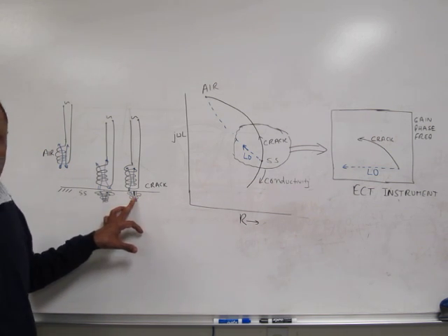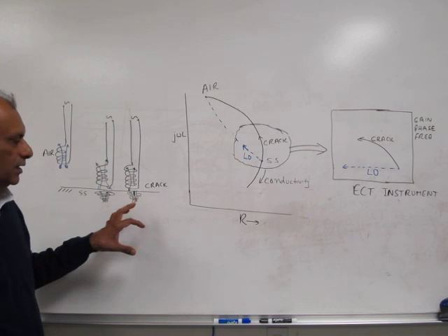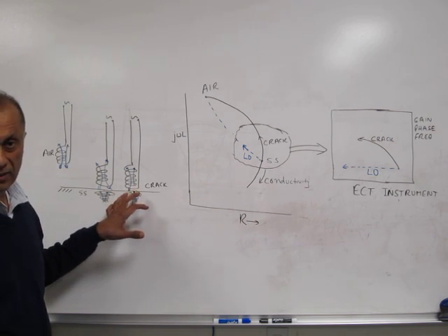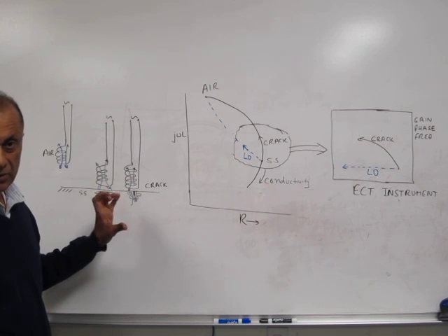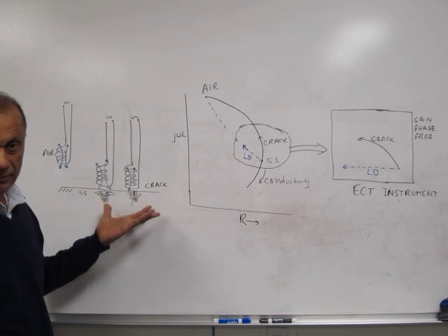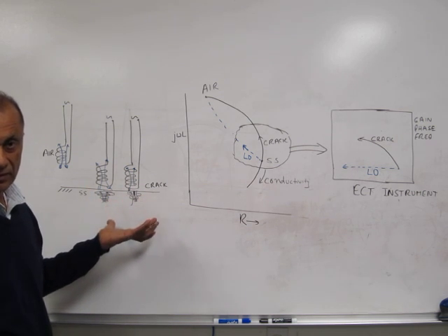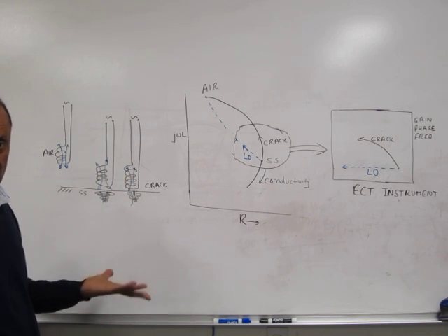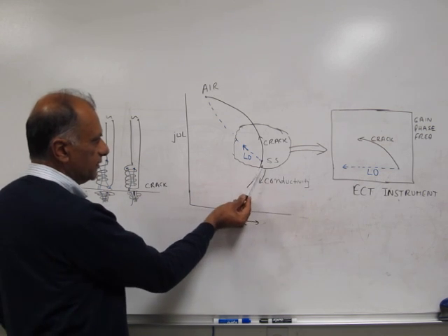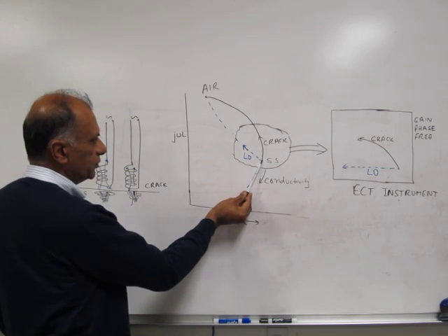As we scan the surface of the stainless steel and encounter a crack, the crack distorts the eddy currents in the material, thereby distorting the magnetic field. This change in the magnetic field interacts with the primary magnetic field of the eddy current coil, changing the impedance of the coil once again.